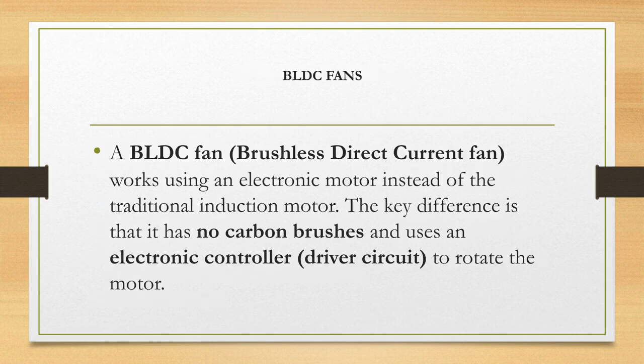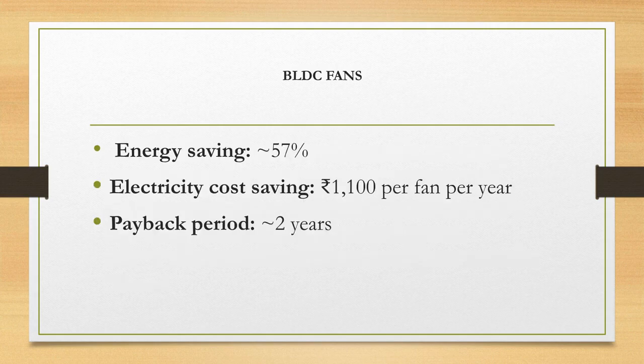A BLDC, or brushless direct current, fan utilizes an electronic motor instead of a traditional induction motor. It lacks carbon brushes and uses an electronic controller to rotate the motor. BLDC fans offer significant energy savings of about 57%, which can translate to approximately 1,100 rupees in electricity cost savings per fan per year, with a payback period of about 2 years.